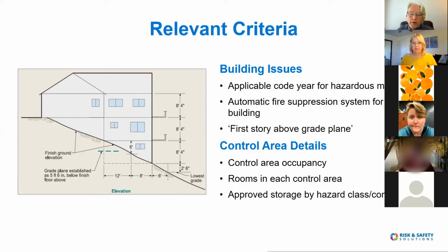You have to know what code year you're applying. There's been a large discussion about what code year applies to a building. Now, clearly, when the building's built, when the plans are substantially complete, is the way the language is written, that's the building code year. And in California, that would be Title 24. That's when the building code is established. When you're using the building, the question is, do you use the same code year as the building year, or do you use the code year that's current?